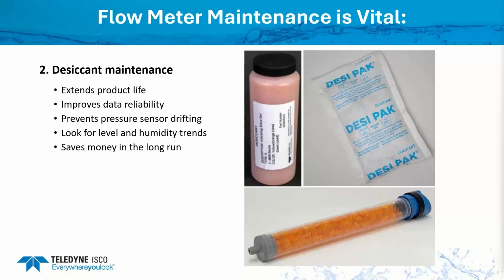The idea of the desiccant is that it draws in the moisture to help prevent any type of corrosion within your equipment. Now, the equipment that you put down in your collection systems faces usually a lot of high humidity in the sewer systems. So you want to make sure that you're using a flow meter that's IP68 rated, so it can handle the high humidity. Most flow meters are designed that way, but there is always a chance for a little bit of air to leak in there, and that's where that desiccant is going to help minimize any type of corrosion.